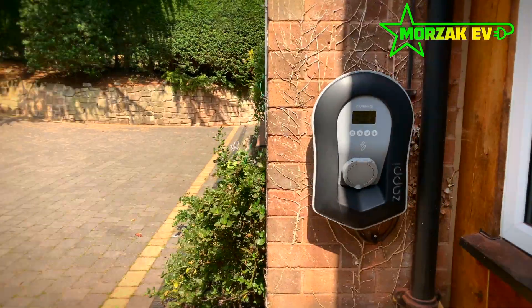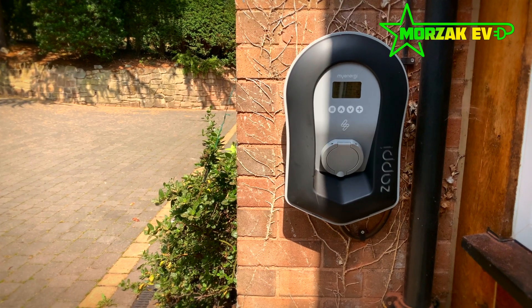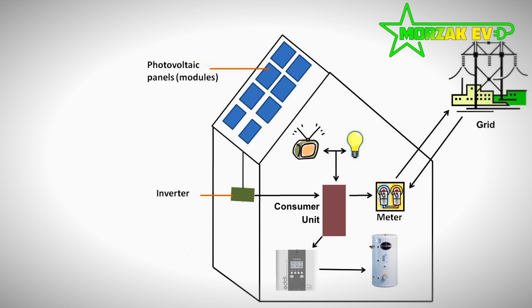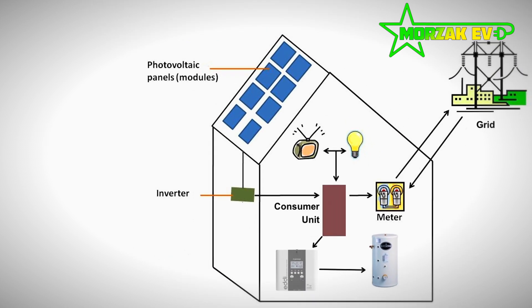A lot of you will know the MyEnergi zappi, and the eddi does the same thing as the zappy but for your hot water tank. We've installed an eddi in between the feed from the consumer unit to the hot water tank's immersion heater. We also put a CT clamp which monitors how much energy is being generated by the solar and how much is being exported to the grid.